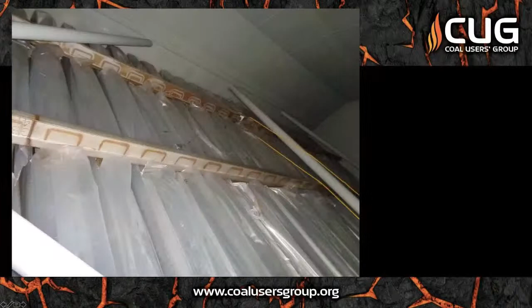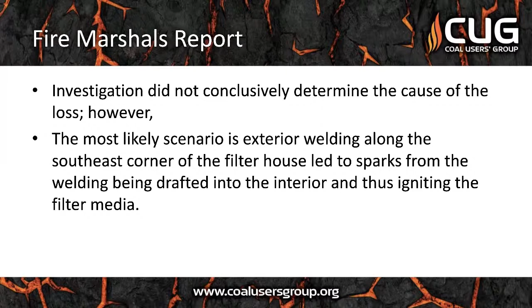So, the fire marshal's report: the investigation wasn't conclusive. They could never determine exactly what caused this fire. They did say the most likely scenario was exterior welding along the southeast corner of the filter house that led to sparks from the welding being drafted into the interior through a couple of open hatches in that direction, thus igniting the filter media.